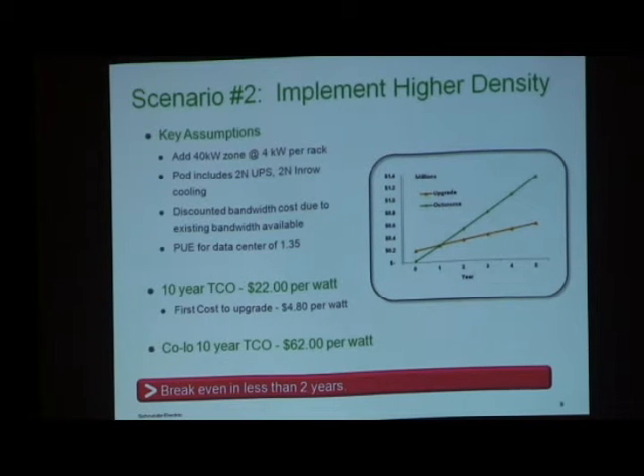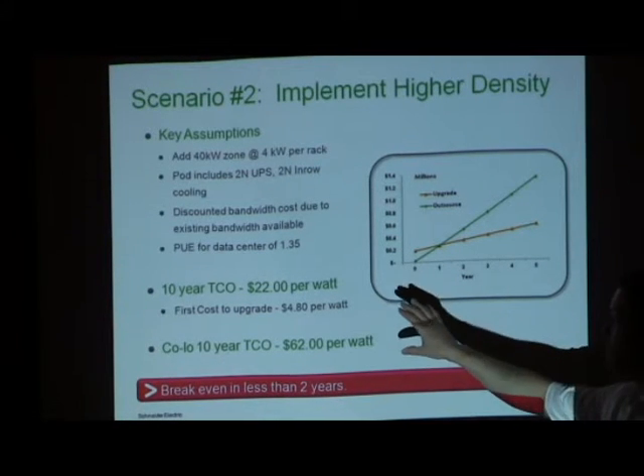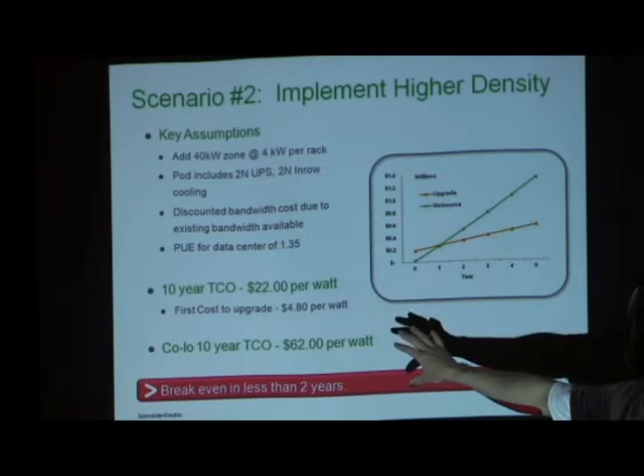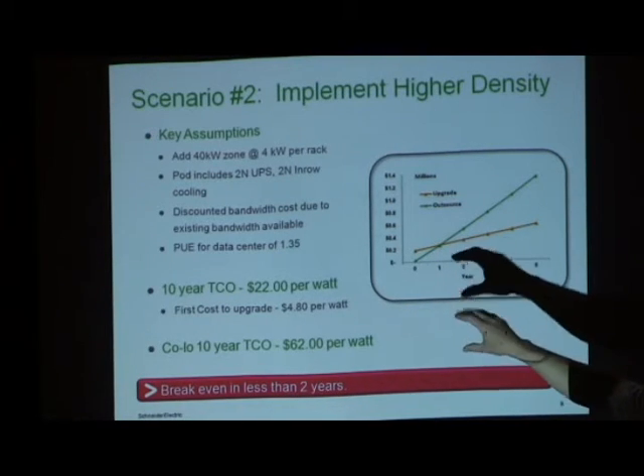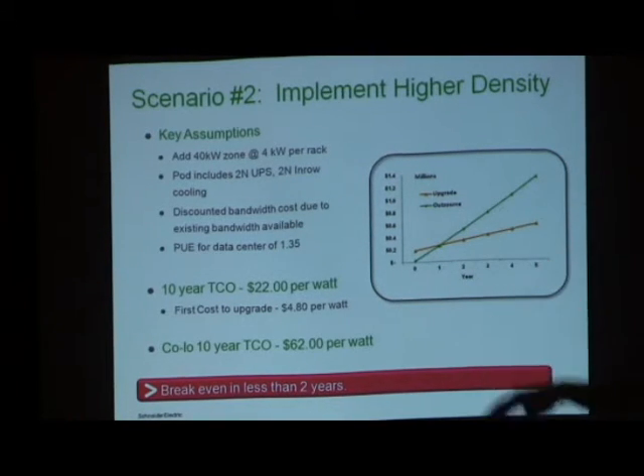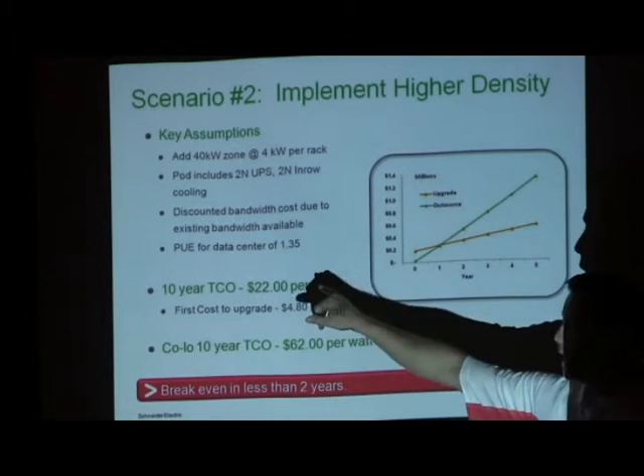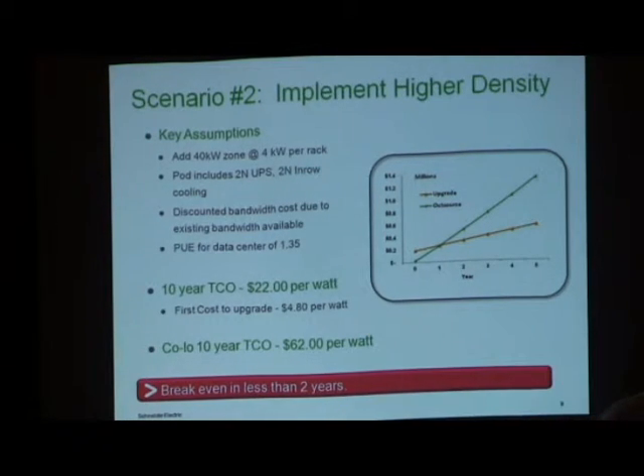Scenario 2, that higher density setup. This would be assuming we're adding a 40 kilowatt high density zone with roughly 4 kilowatts per rack, 2N UPS. What that means is redundancy. You have 2 UPSs, an A and a B side. If one were to fail, the other one can take over the load completely. 2N in-row cooling. And again, I have to preface this by saying this does address having a modular data center approach. A PUE of 1.35. You guys might be wondering what's PUE?